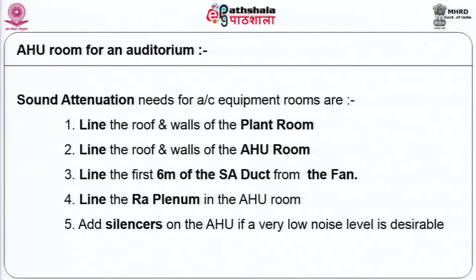Now, when we talk of mass and distance, we have presupposed that these parameters have all been taken care of. In other words, the roof and the sidewalls of the plant room have been lined with absorbent material which attenuates the noise at the source. Next, the AHU room itself has to be lined. Ideally, the roof and all the four sidewalls, but at least two perpendicular sidewalls and the roof is a minimum requirement for AHU room attenuation. Then, the supply duct which goes through the wall should be lined to attenuate any noise which gets into the duct. Minimum 6 meters of duct lining is a requirement. Likewise, for the return air plenum, 6 meters is a minimum requirement.